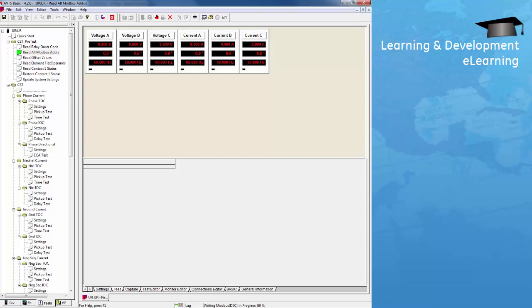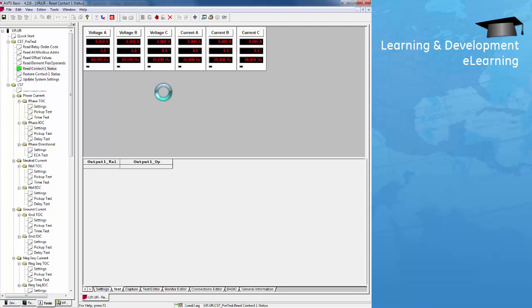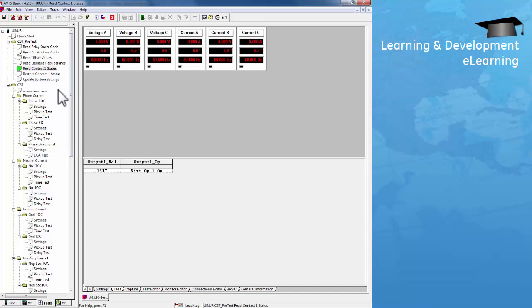Once all three tests are done, we can run the next test: read contact status. Read contact status reads the contact 1 original status, because during the automation test, contact 1 may be temporarily changed for the different protection element being tested. We want to keep its original status and restore that setting at the end of the automation test. For this relay, the original status for output 1 is virtual output 1. This setting is now saved in AVTS and will be restored at the end of the test.